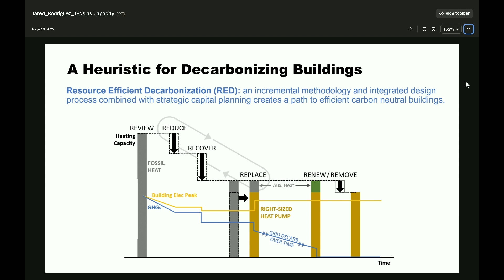And then you can phase in heating and cooling loads over time. Don't try to deal with that peak yet, because that's going to be very expensive. Remember, it's less than 2-3% of the time that your building is ever hitting that peak. So try to deal with all the other loads before you address that, and think about thermal energy storage.